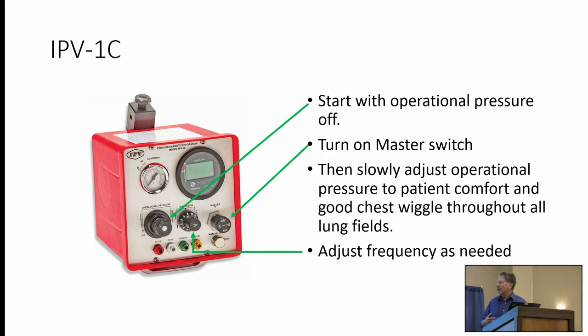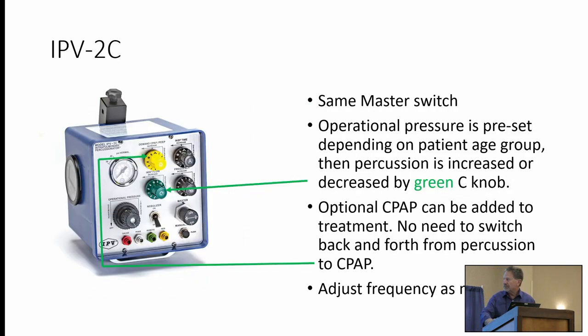The next treatment, you're handing it to them, you're just turning on the master switch. The difference with the IPV2C - this was originally developed so we could do neonatal infants. You preset your operational pressure, and then you have this green C knob, which is how you increase or decrease the strength of the percussion.